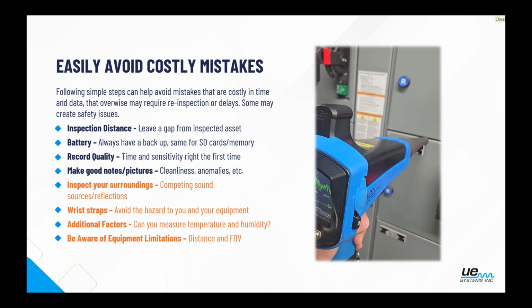You're hearing an event, look around the room. Are there dirty air filters stacked up in the corner of the room? Is there a box fan that should be in a dorm room actually blowing cool air into the bottom of a transformer? So now you know all the dirt from the floor is being blown up into this piece of equipment. General observations of the room might help explain some of the things that you are hearing within that piece of equipment. Also, follow-up procedures that might need to be done.